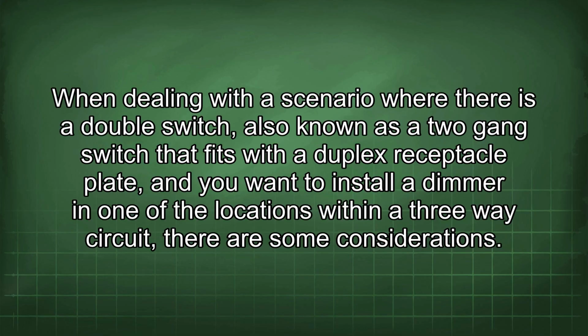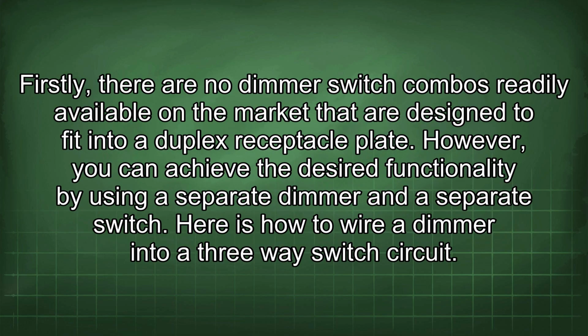When dealing with a scenario where there is a double switch, also known as a two-gang switch that fits with the duplex receptacle plate, and you want to install a dimmer in one of the locations within a three-way circuit, there are some considerations. Firstly, there are no dimmer switch combos readily available in the market that are designed to fit into a duplex receptacle plate. However, you can achieve the desired functionality by using a separate dimmer and a separate switch. Here is how to wire a dimmer into a three-way switch circuit.